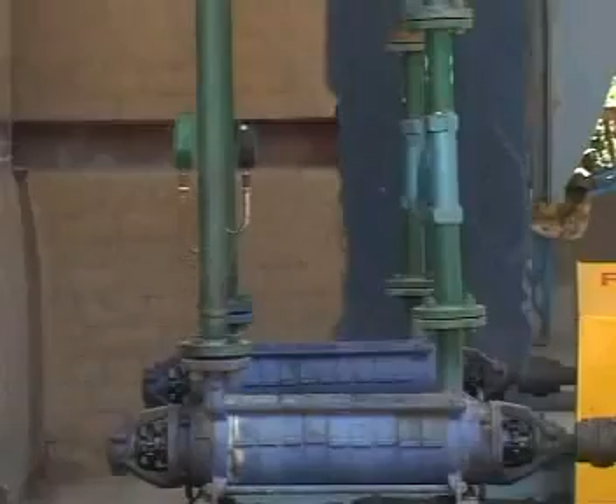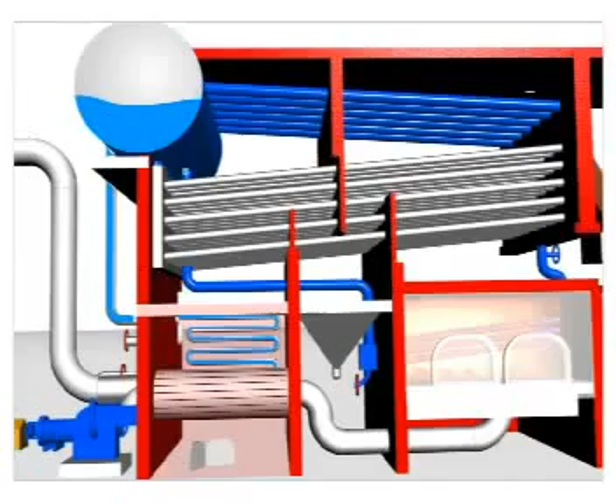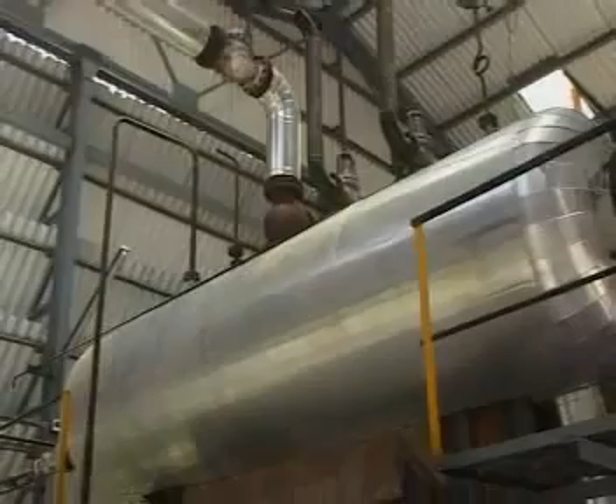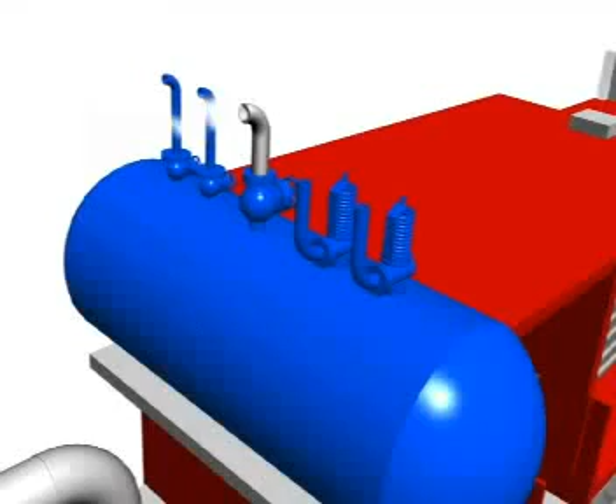Feed water pump supplies water through waste heat recovery economizer to the boiler drum. From boiler drum, water moves to convective bank tubes and radiative furnace in-bed cooling tubes because of thermal gradient. Eventually, steam is formed by counter current convective and radiative heat transfer. The mixture of hot water and steam reaches the drum through riser pipes. And finally, steam is taken out of the drum through main steam valve after passing through steam purifier.